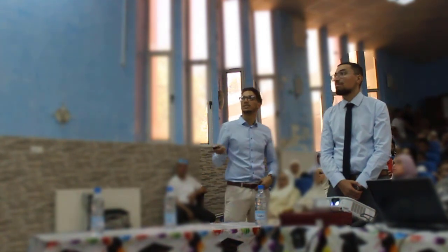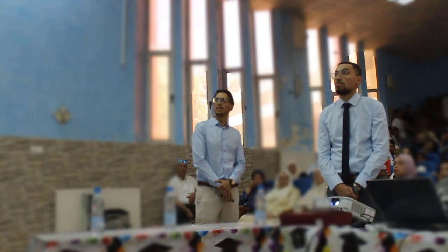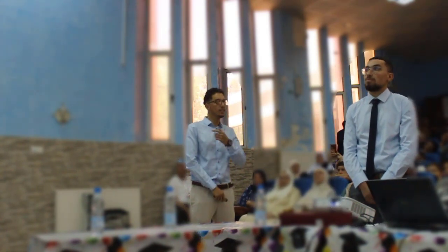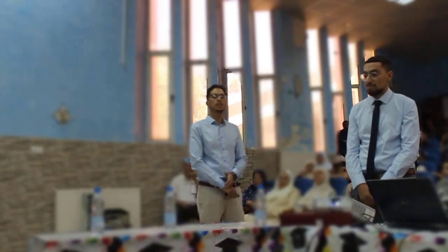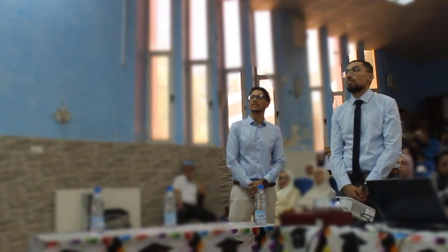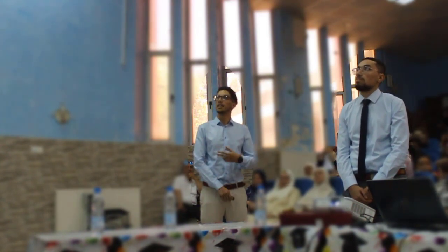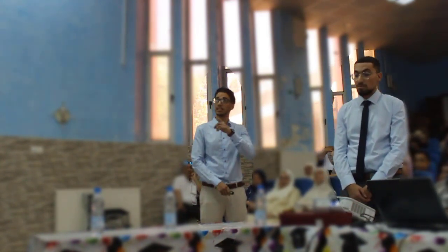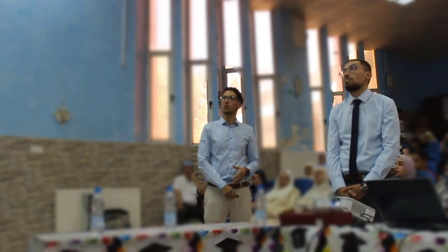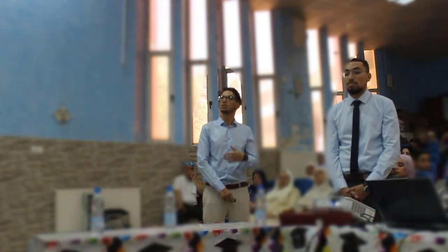So probably the best question you are asking yourself is, what is a gamma ray spectroscopy system? Well, basically, it is a radiometric tool that collects and monitors data in order to provide us with a spectrum at the end. So why do we want the spectrum, or what does the spectrum represent? In our context, a gamma ray spectrum is simply a histogram that represents the emitted number of gamma photons from each energy level that we call the channel. In other words, it shows how many counts of gamma photons belong to each channel.